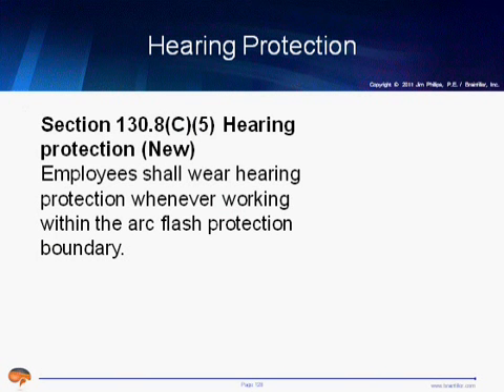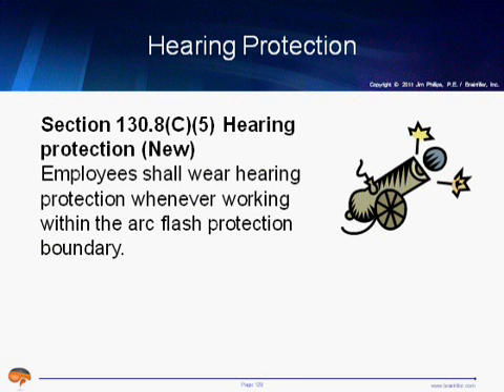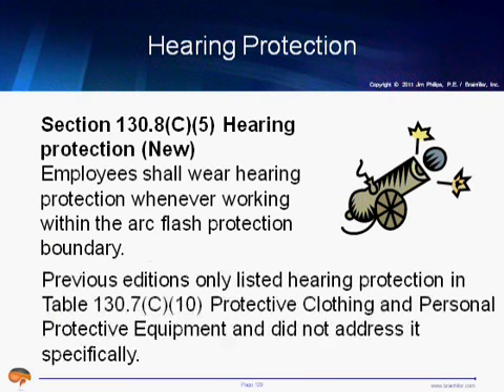Hearing protection has been included in the past in NFPA 70E, but it was really just listed in the tables of what PPE to wear. So beginning in 2012, they're going to be more specific about hearing protection, and it's to be worn when you are within the arc flash protection boundary. And hearing protection, in my view, is quite important. When I've been in the lab, even low-level incident energy shots of like 1 to 2 calories per square centimeter, to me, it sounds like somebody has a gun going off next to your head. And it's quite loud. And if you're involved in a more explosive arc flash, well, it can cause some serious and permanent hearing damage.